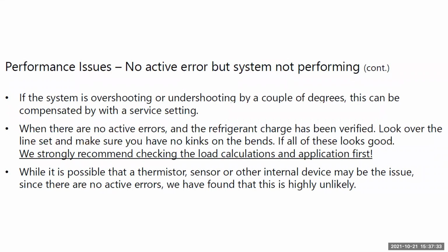You also want to verify your flare nut works. Also, if you have overshooting or undershooting by a couple degrees, sometimes we can utilize the temperature compensation and take that out of this scenario, and it'll fix it. We strongly recommend you do a load calculation if you're getting a lot of overshooting and undershooting. It is possible for a thermistor or internal device to be the issue and there not be any active errors. That's why sometimes we want to check against the chart.